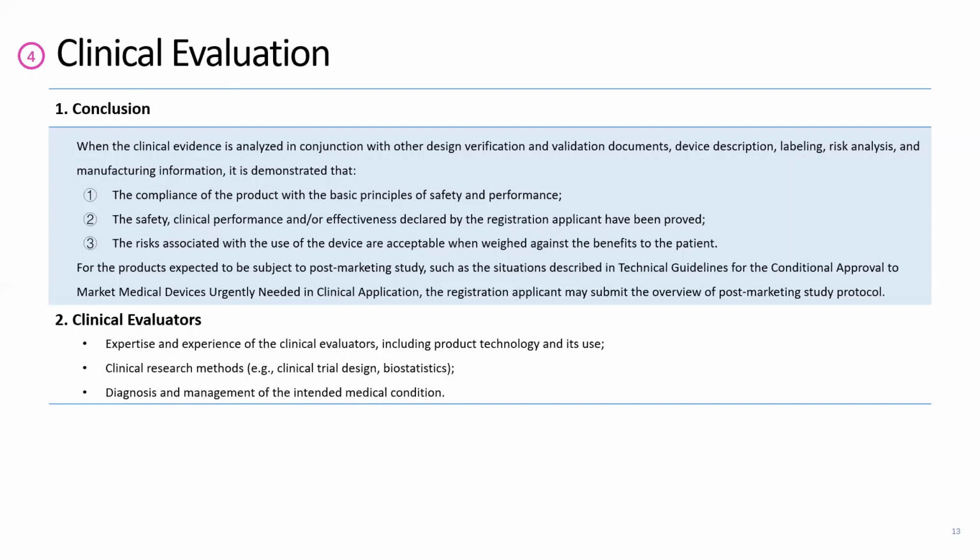This conclusion should cover 3 parts. The first part, as Grace has mentioned, is that we need to comply with the ER. The second is about our clinical part, that we need to support the safety and the efficacy of our data. The third part is the most important because it is newly added in the guidance: we must evaluate the benefit and risk, whether we can get benefit from the subject device.